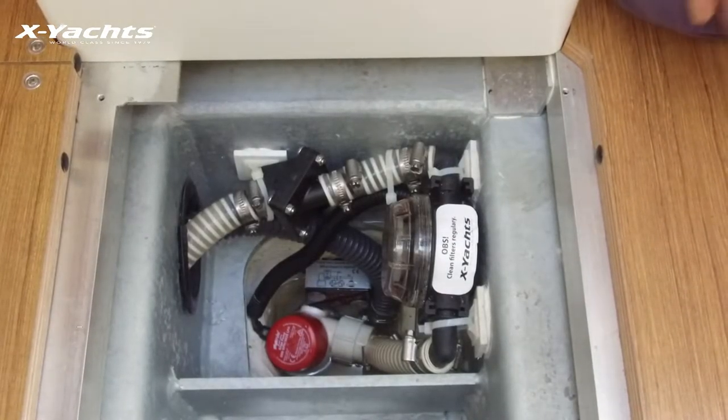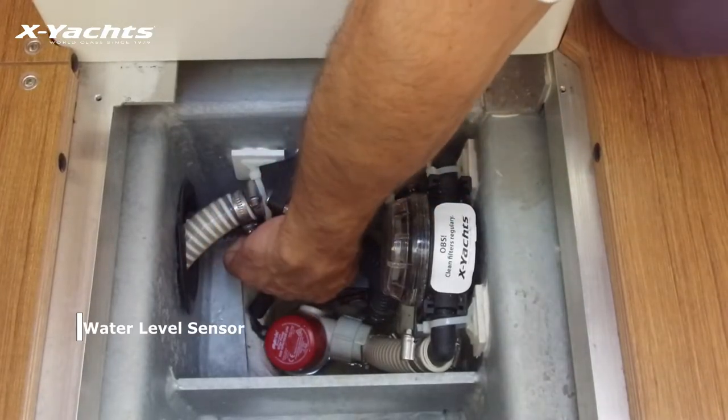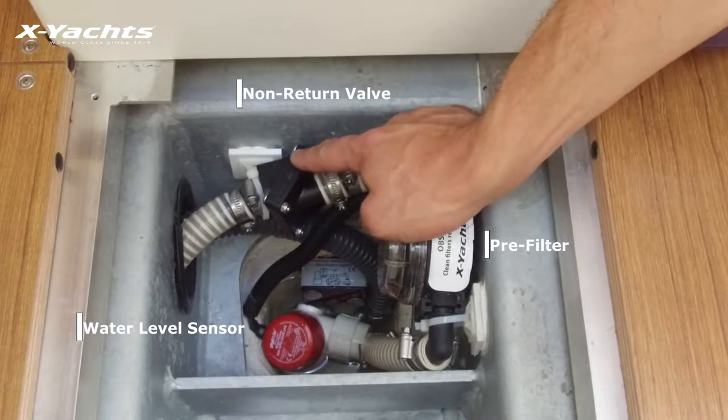Hello, this is Julian Renaud from X-Yachts Great Britain, Head of Service. Today I would like to show you how to inspect your electric bilge sump pump. The electric bilge pump system is fitted with three items: the sensor at the very bottom of the sump, the pre-filter, and the non-return valve.